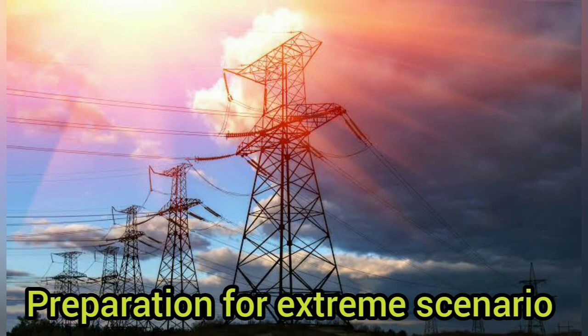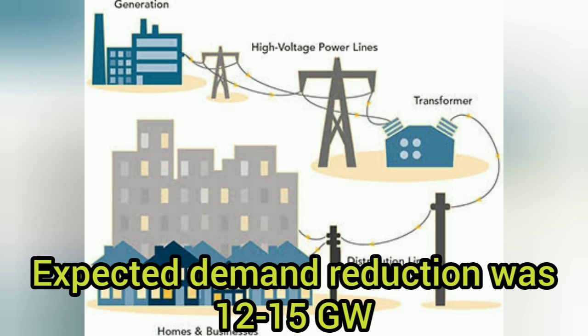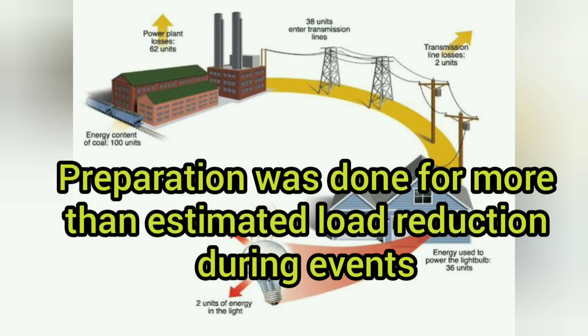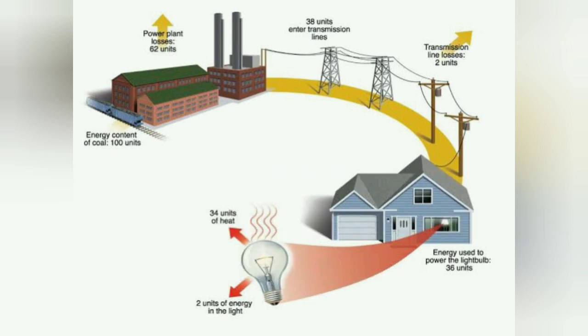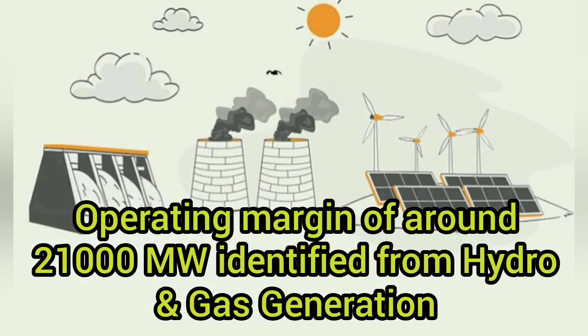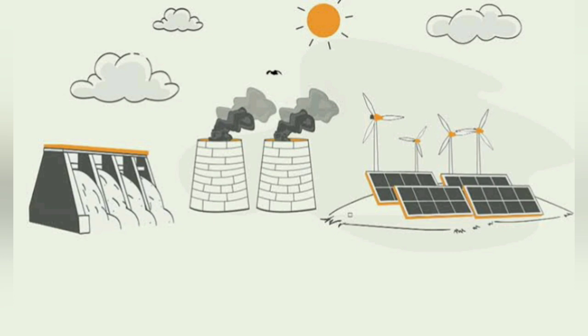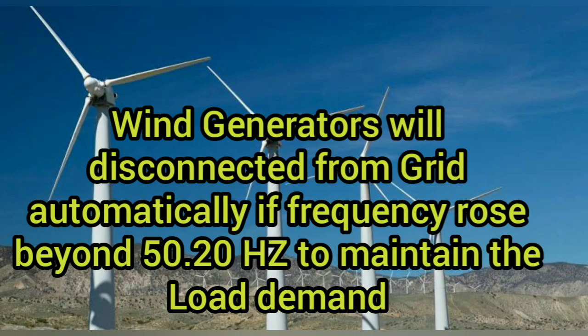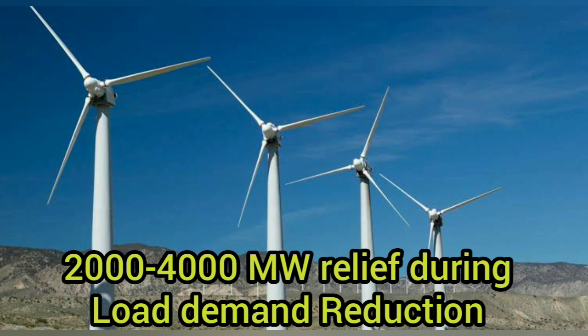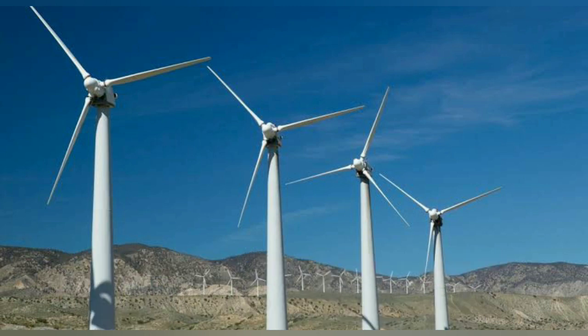The preparation for the extreme scenario was also done. The demand reduction during the event was anticipated at 12 to 15 gigawatt, and preparation was carried out for the extreme scenario, that is, much larger demand reductions than anticipated. Operating margin of around 21,000 megawatt was identified in hydro and gas generating resources across the country with SLDC, ISGS, hydro and gas generating plants. Enabling over frequency setting of wind generators ensures tripping of wind turbines if frequency rises beyond 50.20 Hz. That relief of 2000 to 4000 megawatt will be achieved from these resources.